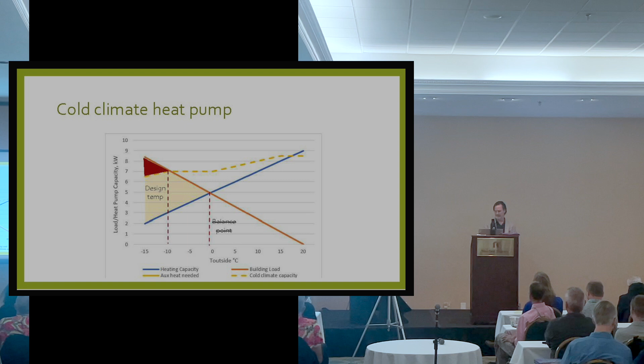And as you can see, at the same design temperature, we're actually meeting the load. And we might want to put in, for that dark red triangle, just a little bit of some sort of auxiliary heat to make up just the difference for those extreme weather conditions, for those 12 hours a year that it goes below the design temperature. Depending on the project and depending on the client, that may or may not be important.